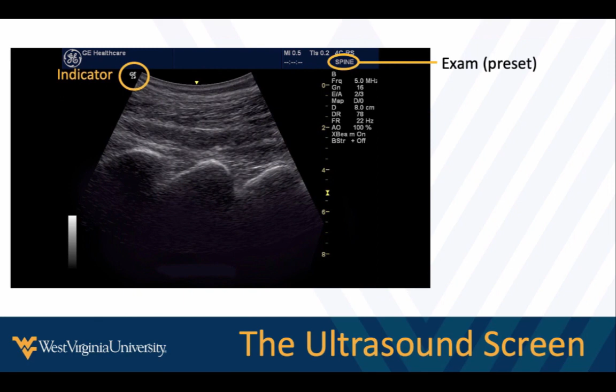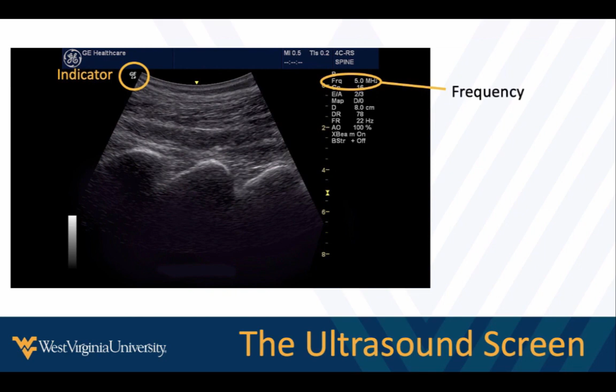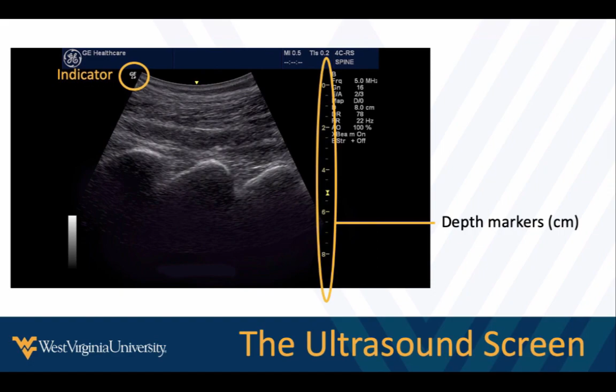The frequency, you may or may not be able to adjust this a little bit, but you want to make sure that if you're looking at the heart of a 300-pound linebacker, you're not at 16 megahertz frequency, because you're never going to see anything. The max depth is usually listed over here. It's good to know where your depth is. The depth, along with the gain, are the 2 controls you're actually going to need to mess with a little bit as you're scanning your patient. And then by most conventions, there are depth markers on the sides that can help you not only see what your depth is on the screen, but you can also use these to eyeball sizes of things. If you see, okay, this is roughly what our scale is for structures on our screen, that helps us eyeball estimate sizes.